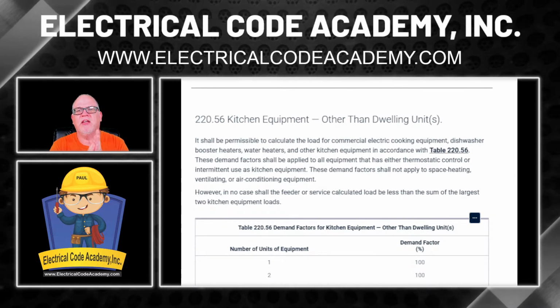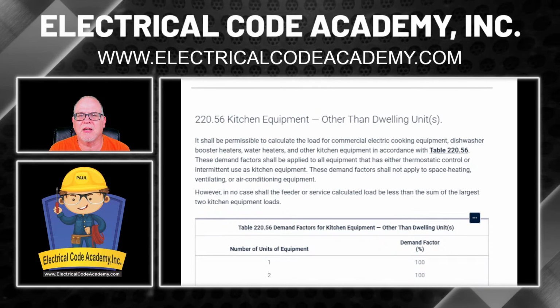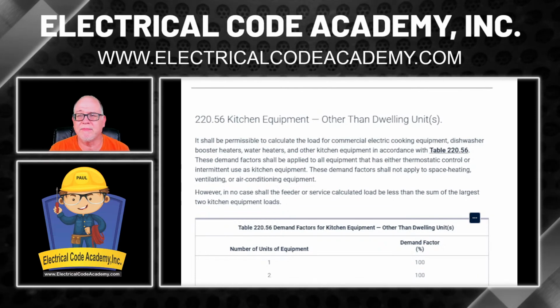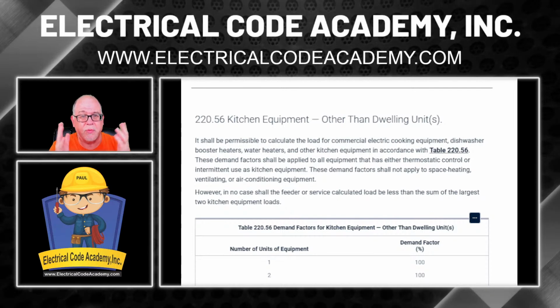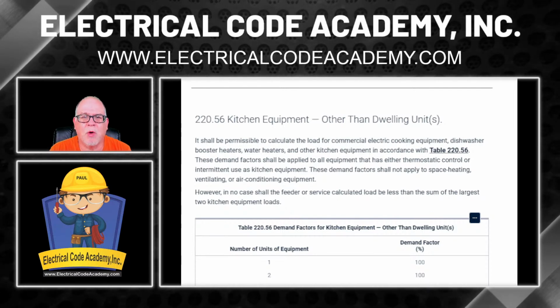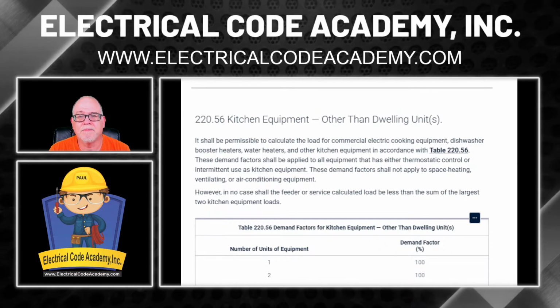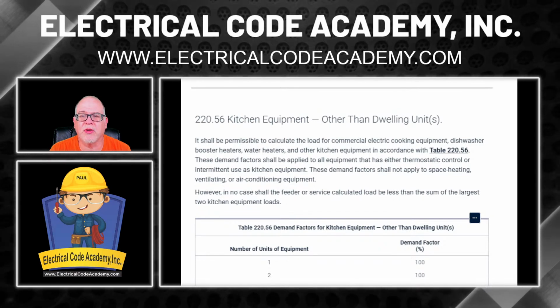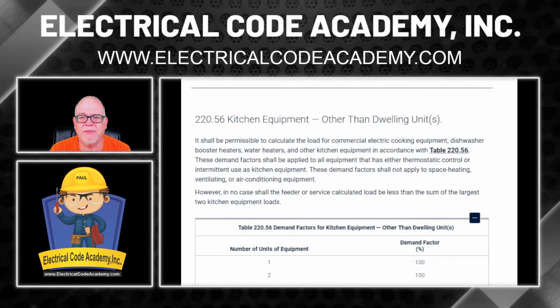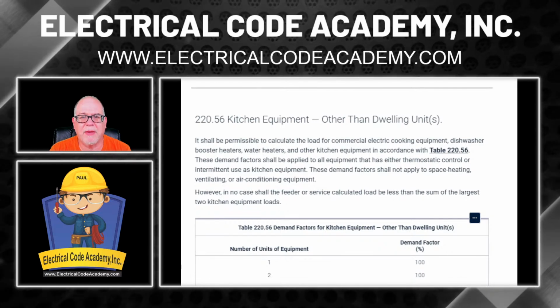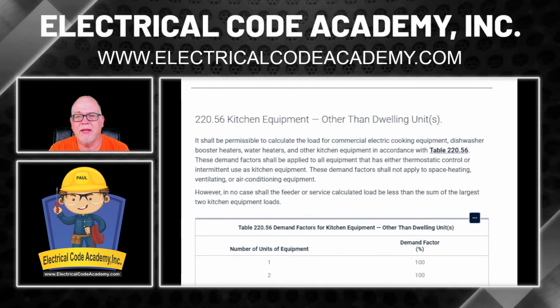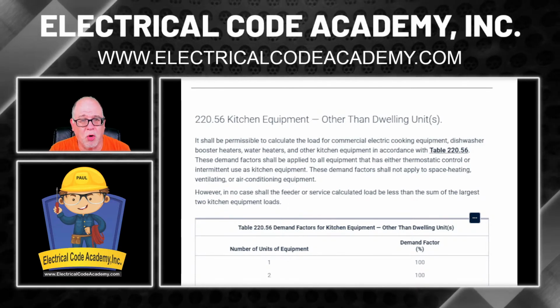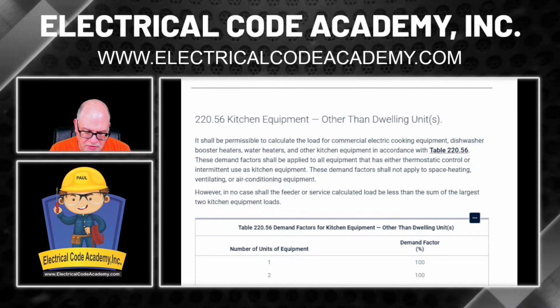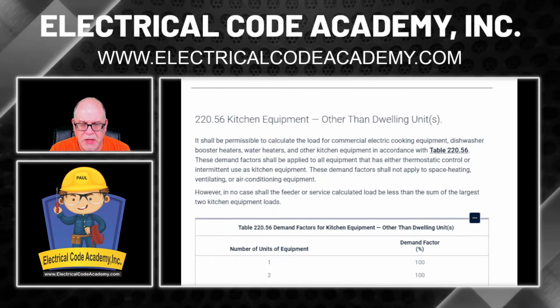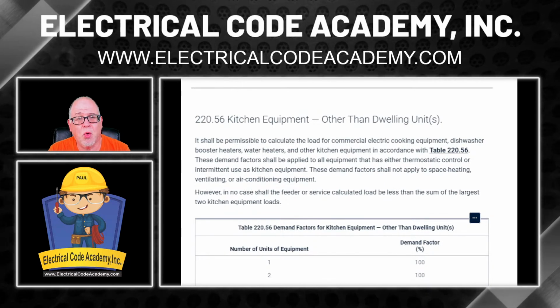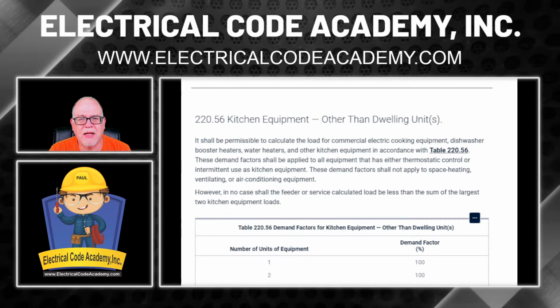So let's read it. It says, it shall be permissible to calculate the load for commercial electric cooking equipment. Okay, so we do have cooking. We have ovens, so we're good there. Dishwasher booster heaters. We do have a booster heater. Water heaters and other kitchen equipment in accordance with table 220.56. It also says these demand factors shall be applied to all equipment that has either thermostatic control, and most of this stuff, the ovens, the grills, the deep fryers, and all that kind of stuff, are going to be thermostatic controlled. It says, or intermittent use in as kitchen equipment.